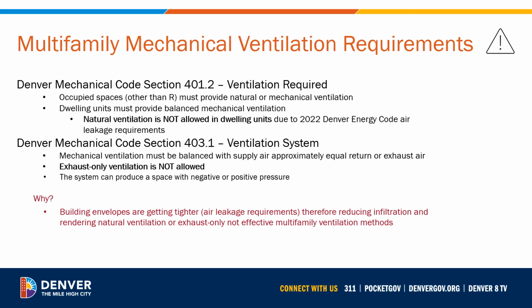Due to the 2022 Denver Energy Code air leakage requirements covered on the previous slide, the Denver Mechanical Code states that ventilation must be provided by mechanical means to all dwelling units regardless of building height. This means dwelling units are not allowed to rely on natural ventilation via operable windows. Furthermore, the Denver Mechanical Code does not allow for exhaust-only ventilation as a mechanical ventilation strategy in any building type. Where mechanical ventilation is provided or required, such as in dwelling units, ventilation must be provided by a combination of supply and return or supply and exhaust air.